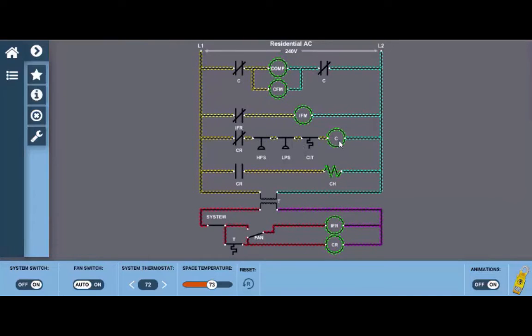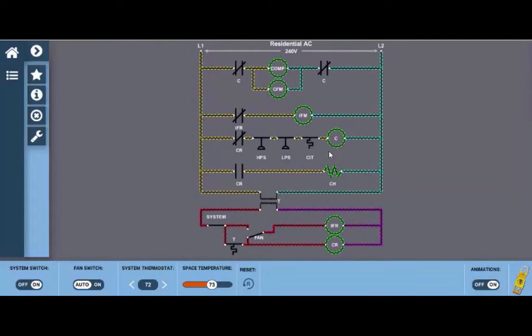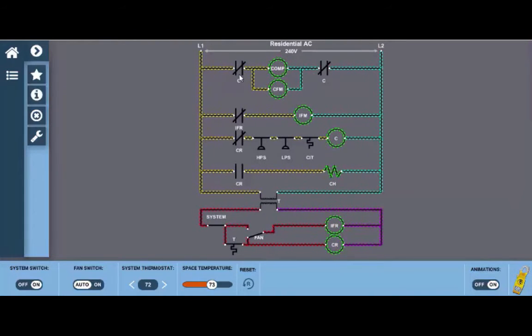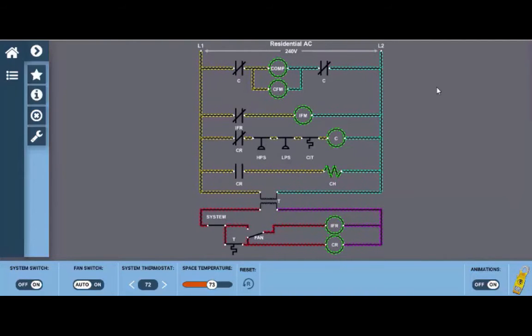So we're basically using a relay to turn on another relay here. When this relay coil within the contactor energizes it closes its two contacts up here which provides power to the compressor and condenser fan which we can see is running.